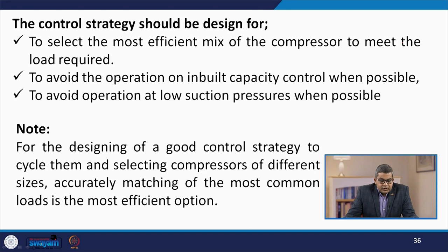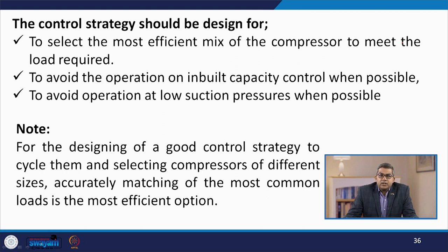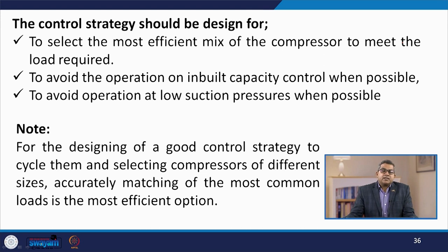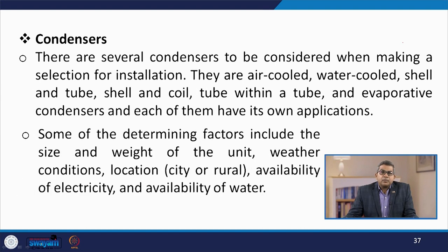The control strategy should be designed to select the most efficient mix of compressors to meet the required load, avoid operation on built-in capacity control when possible, avoid operation at low suction pressure when possible, and cycle compressors while selecting compressors of different sizes to accurately match the most common loads for the most efficient operation.